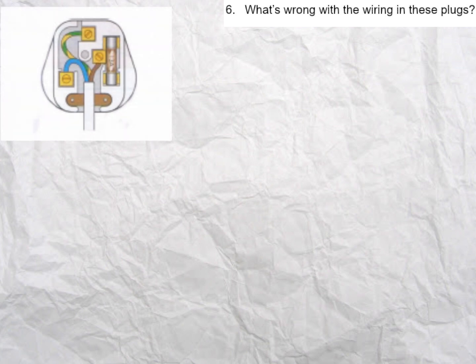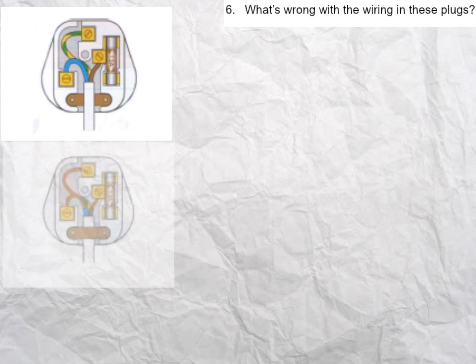The first plug has the cable not held by the cord grip, so we'd have to use the grip and tighten it up. The second plug has all the insulation stripped way too far back, exposing the copper wires and allowing them to touch. We'd have to trim off all that excess copper wire, give it a bit of a haircut, and rewire the whole plug. Don't laugh, I've seen plugs wired like this.